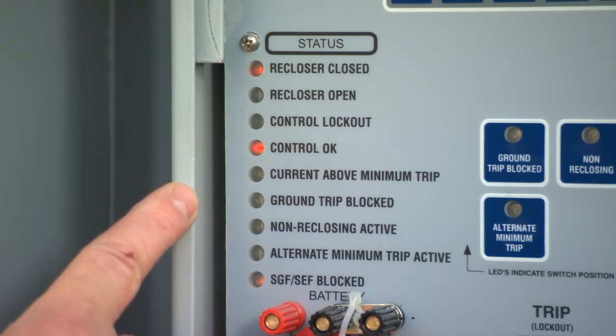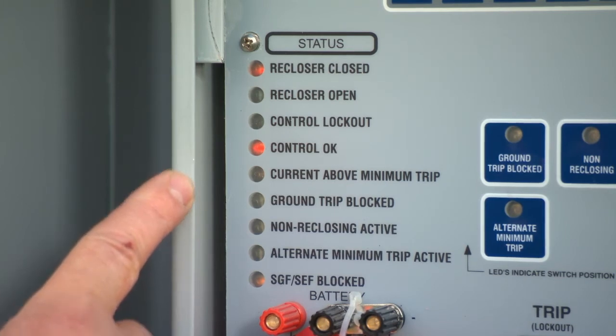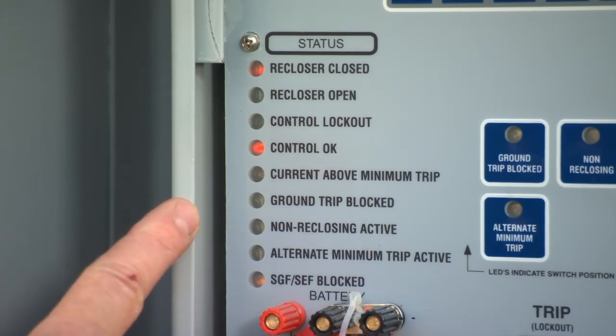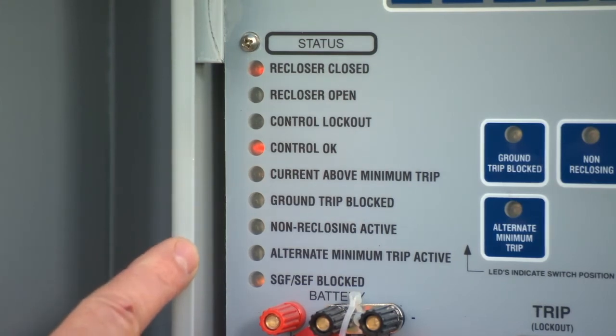While there is a fault being applied, the current above minimum trip LED will illuminate. Ground trip blocked will illuminate when the ground trip button is applied. This is used to tell you that the ground is blocked. Next is non-reclosing active. This indicates that the recloser will not reclose after an operation. This is identical to a hold-off or hotline tag.